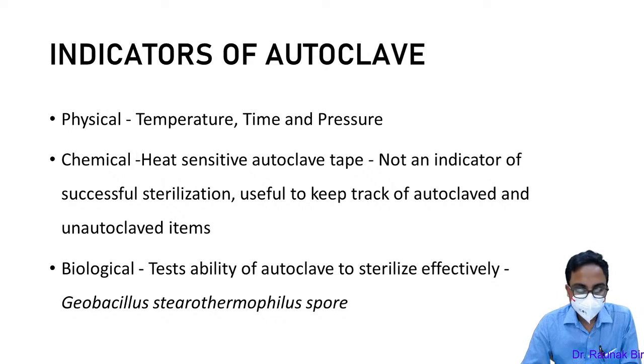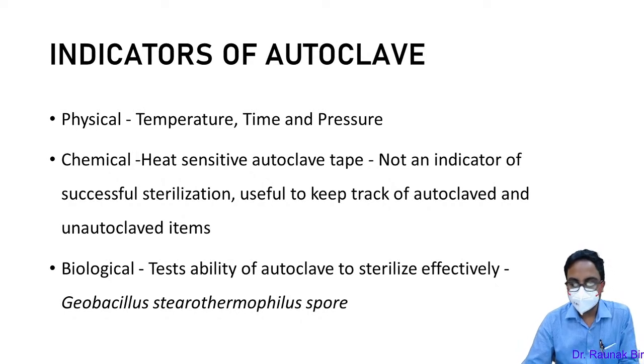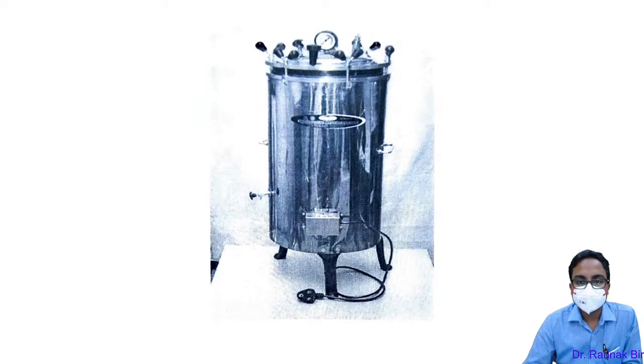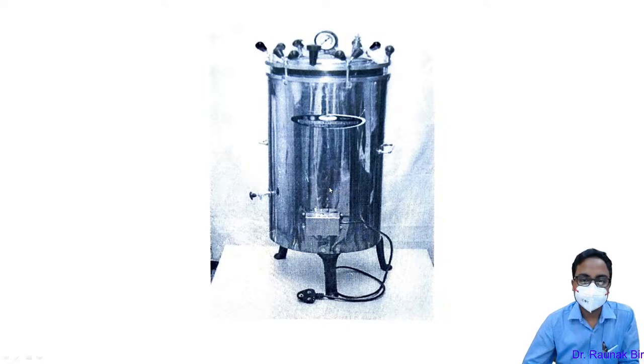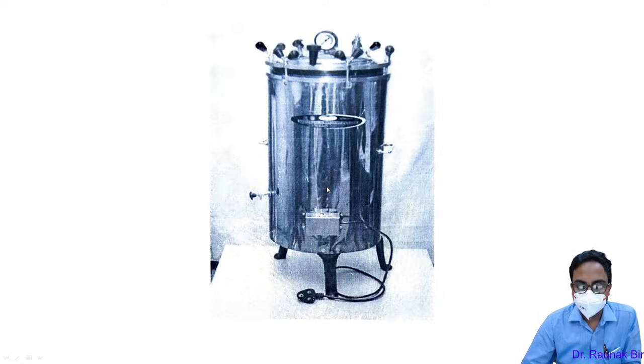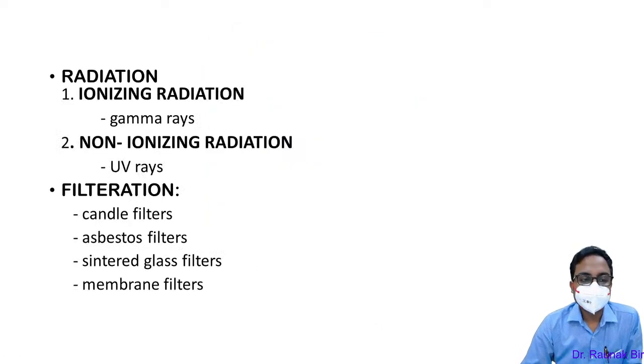Small vials containing Geobacillus spores are incubated at 60°C for 48 hours after autoclaving. If there is growth, there is a failure of that day's autoclave run and we must discard and redo the autoclaving. The autoclave has a pressure gauge, safety valve, and metal jacket. Articles should be placed so that steam can pass through; they should not be jammed together, as that can create a negative pressure area where steam may not reach.